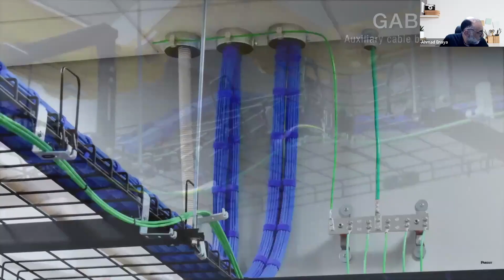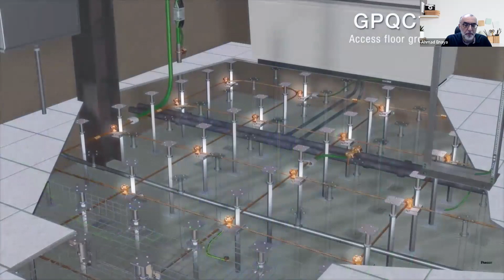This means ensuring ladder racks and cable tray sections are electrically continuous, any armored cable is properly bonded, and any exposed building steel and conduit are also connected to the bonding network and back to the bus bar. If you have a supplemental bonding network or below floor reference grid, make sure that either the electrical contractor or a data center technician connects it properly to the support posts as well as to the secondary bonding bus bar. So everything, even the mesh, is at the same level.